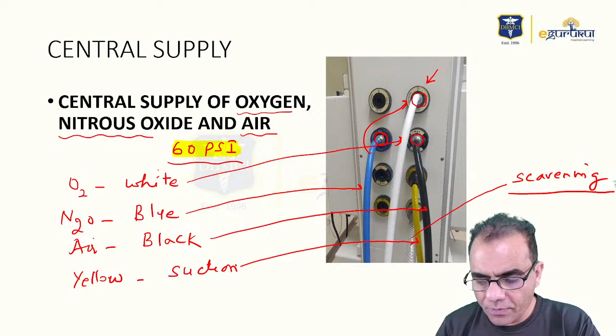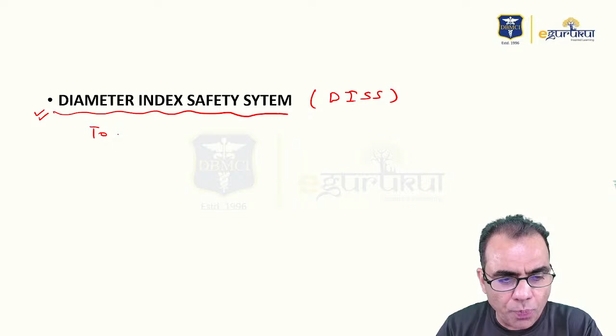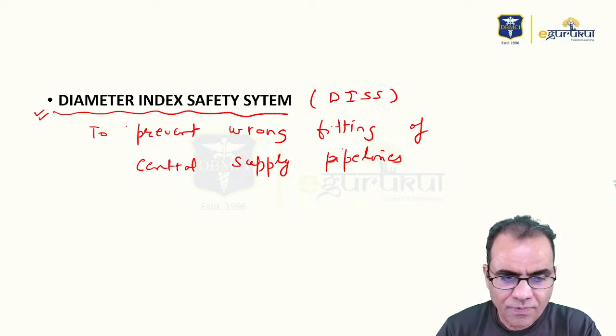Similarly, air also will not be able to fit at the place of oxygen because the slot for air is different, having different diameter from the slot of oxygen or nitrous oxide. So each pipe has different diameter which can fit only in the socket meant for that pipe. So the diameter index safety system is to prevent wrong fitting of central supply pipelines.